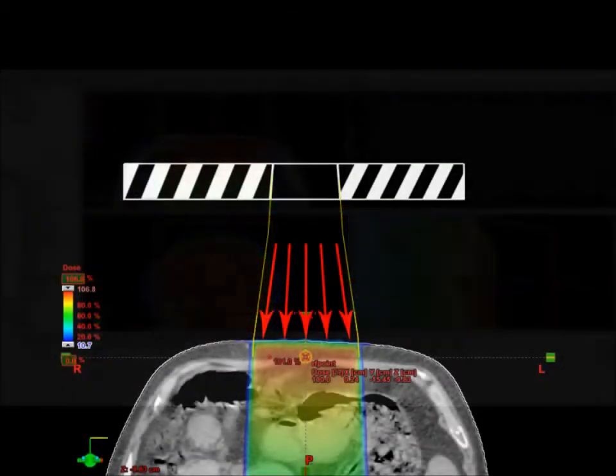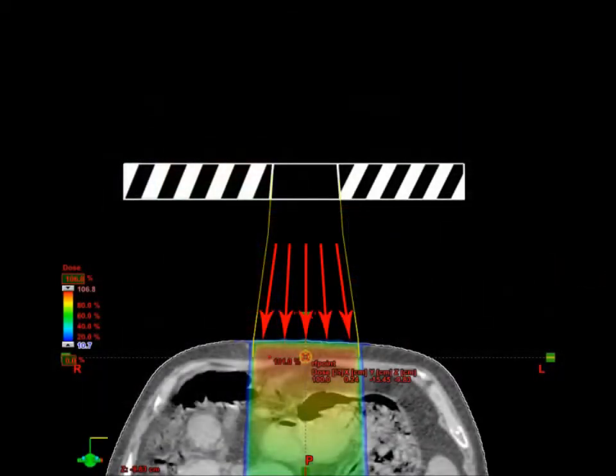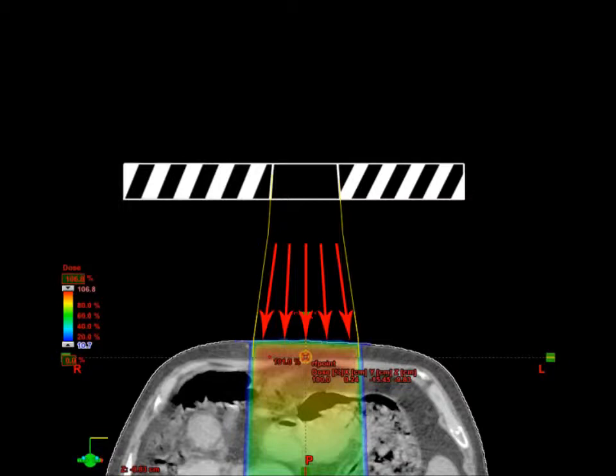Here I've done an exaggerated example of a collimator and the scatter coming from it. The red arrows represent the scatter, and the dashed white lines are the collimation jaws. We have a 10x10 here, and we can see this scatter going through the portal, hitting the skin.